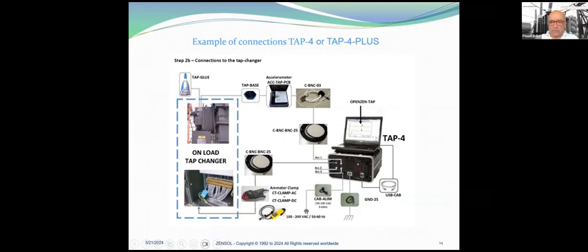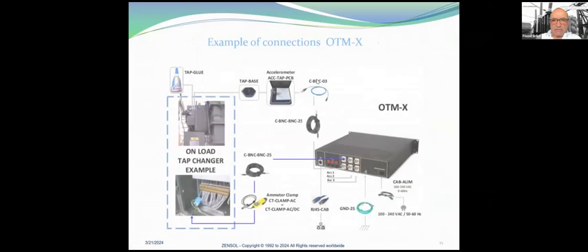And the connection between the computer and the recording system is done through USB for the portable TAP-4. Here you have exactly the same, but using an OTMX, which is a standalone event recorder. So it's exactly the same, but this one acts exactly like a monitoring system. So you can leave it there for months and years connected to your tap changer.